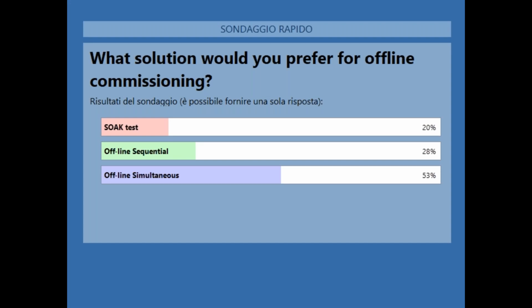Thank you, Jessica. So I see that, let's say, my lesson was appreciated by the audience as well. From a diagnostic point of view, the simultaneous test is always a preferable solution. There is normally a little bit more problem to find the resources to have a big testing team and to manage this testing team in order to work all together during the single 1 hour of HVAC. But that, of course, is better for the cable. So we are testing that cable at our higher voltages just one time.